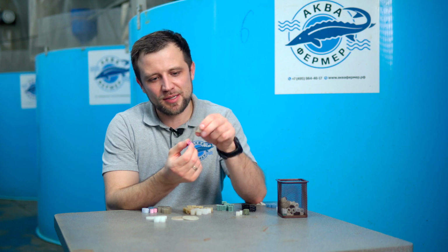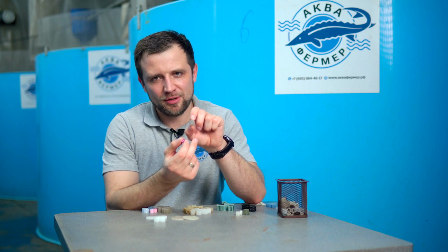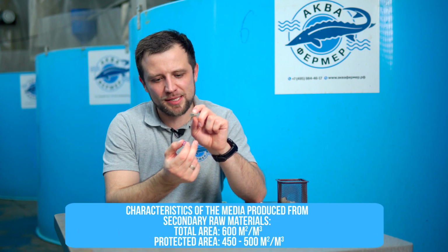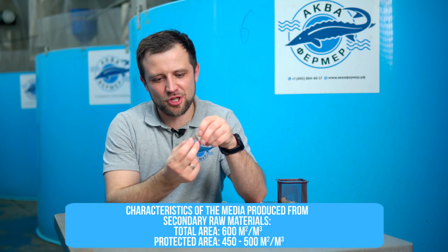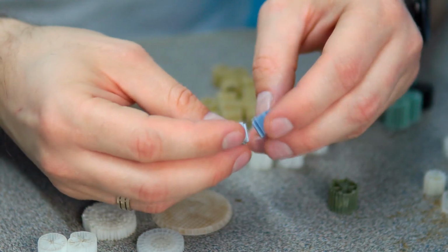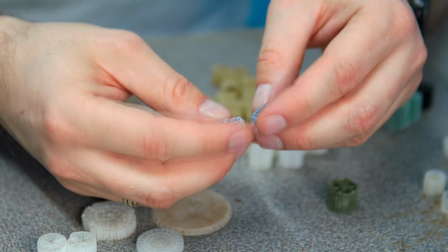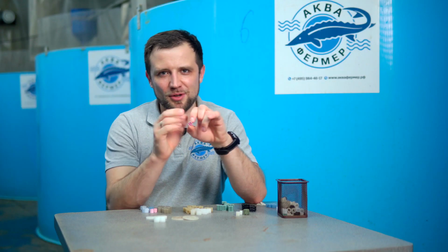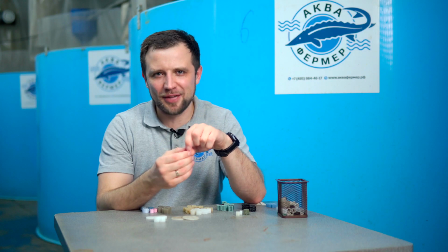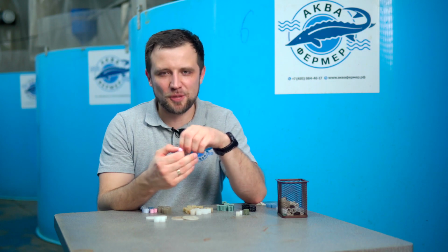Also, as you can see by its characteristics, this media can cover 600 square meters in total, maximum 450–500 square meters of protected area. This one is bigger in size, and it has a significant disadvantage, which is the difference in caliber. There were lots of small-sized media pieces. It kept slipping and penetrated into the pumps, so we had a whole bunch of problems with it.